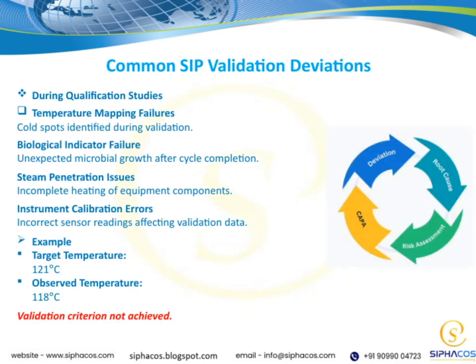When we talk about common deviations during SIP validation, a few issues tend to come up. Temperature mapping failures happen when cold spots show up during the validation process, spots that don't reach the required heat. Biological indicator failures mean unexpected microbial growth appears after the cycle, signaling a problem. Steam penetration issues occur when parts of the equipment don't heat properly. And instrument calibration errors can throw off sensor readings, skewing the data. For example, if the target temperature is 121 degrees Celsius, but we only observe 118, the validation criteria aren't met.